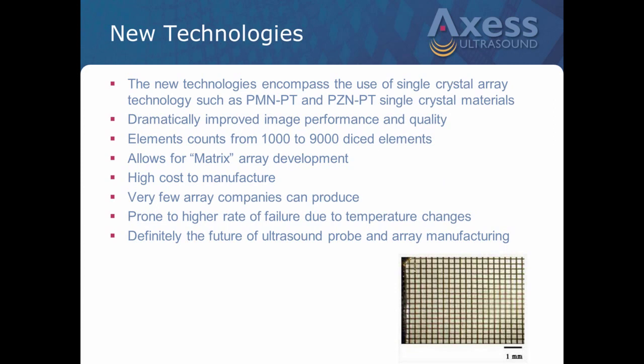Element counts, even though, as I said, they're not individual elements, they are diced in a matrix grid, as you can see down here in the lower right, but this is all one piece of array crystal material. Theoretically, it allows you to have from 1,000 to upwards of 9,000 elements if you were looking at it as an individual element type of probe. It allows for something that some of the manufacturers, especially Philips, are using called matrix array development.